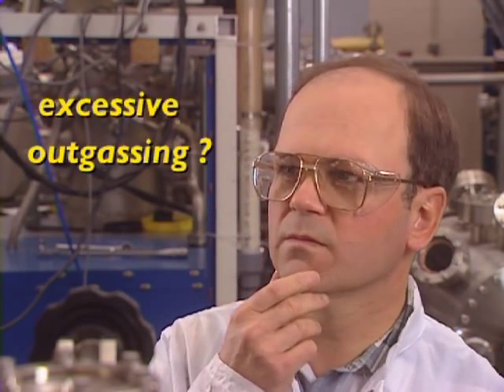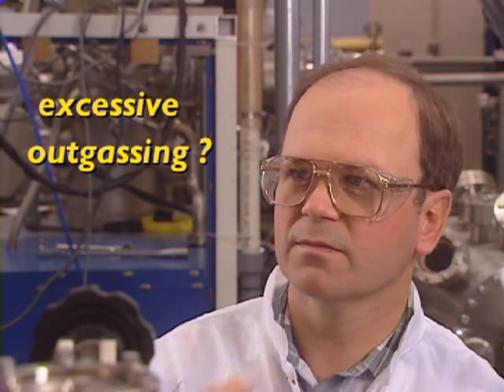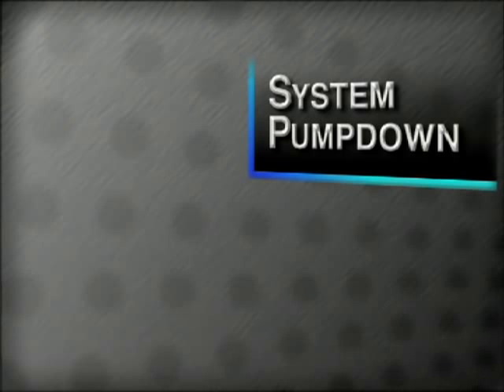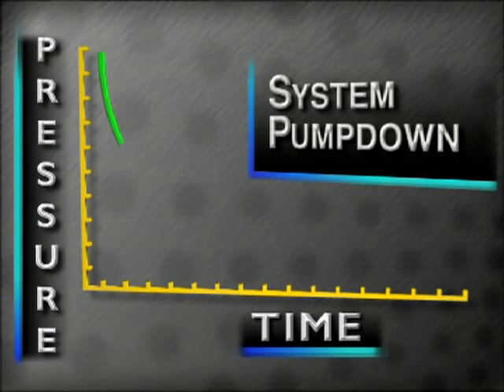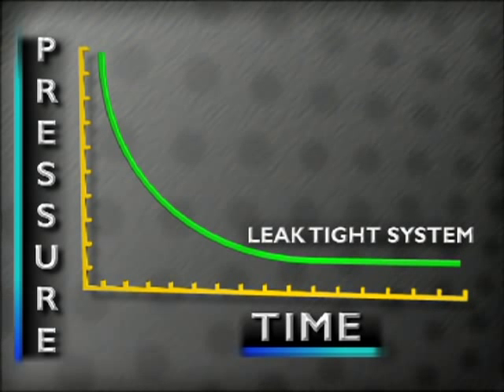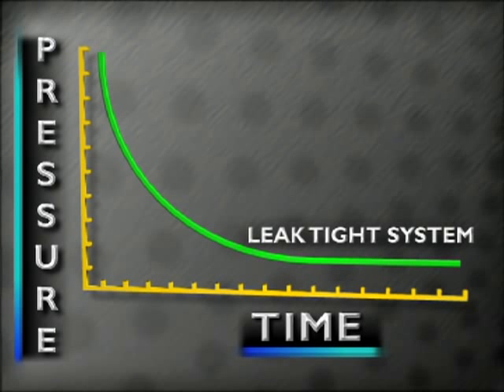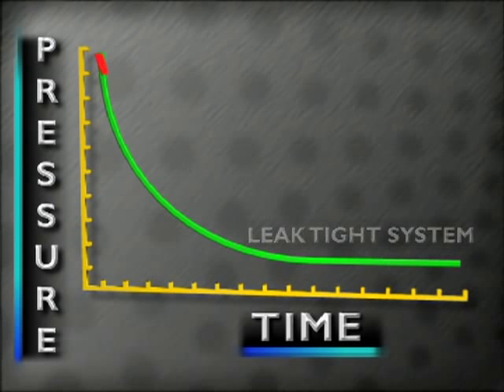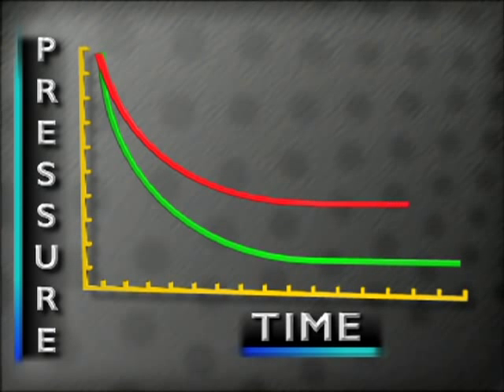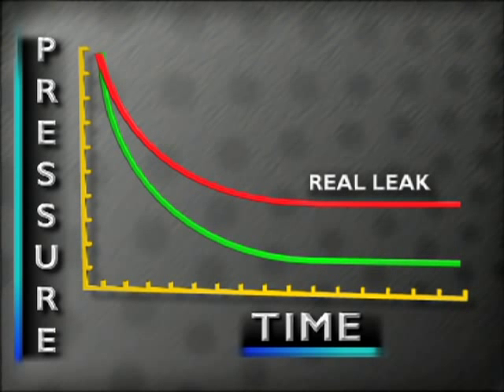The types of leaks include a real leak, an internal leak, or a leak due to excessive outgassing. During the evacuation of the vacuum chamber — a pump-down — the pressure will drop to a certain point in a given amount of time. If a real leak exists, outside air continuously enters the vacuum chamber through an opening. During a pump-down, the pressure will not fall as fast or to the same ultimate pressure as when the chamber is leak tight.